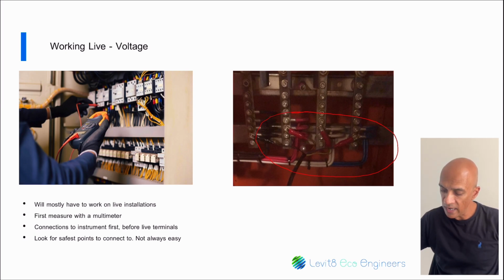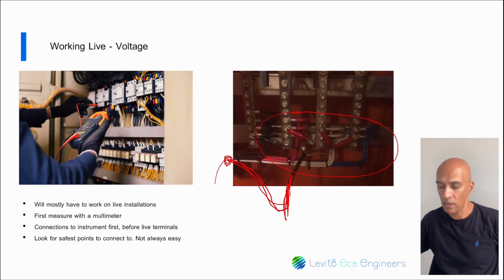Now these crocodile or alligator clips need to be secure and not weighed down by the weight of this cable coming here. So I usually try and find a location on the side, perhaps on the side of the panel, and I try to cable tie that cable so I don't have too much cable hanging down here and too much weight on those crocodile or alligator clips. So it's very important to do that and always keep cable ties with you.